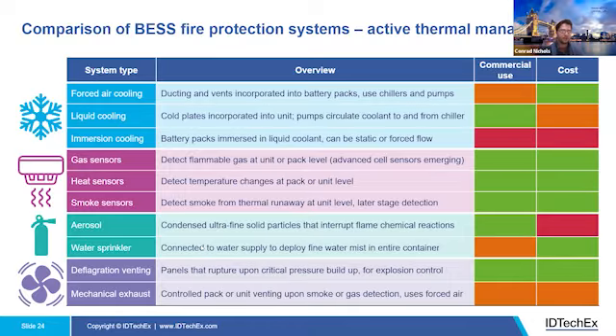And preventative technologies are vital to mitigating thermal runaway risk. And while traditional unit level sensors like smoke or gas detectors help to alert operators to a fire event, they can often identify problems too late, when the thermal runaway event is already happening. And so there's ultimately opportunity to integrate advanced sensors at the pack or the cell level to detect early off-gassing. And this could enable earlier intervention and system shutdown before a full-scale event occurs.